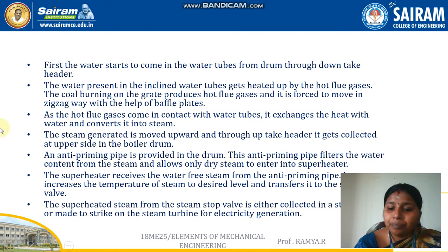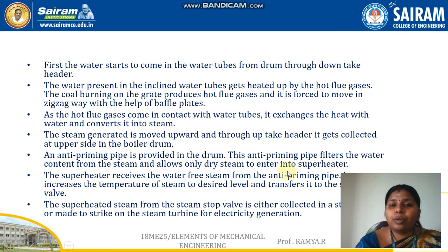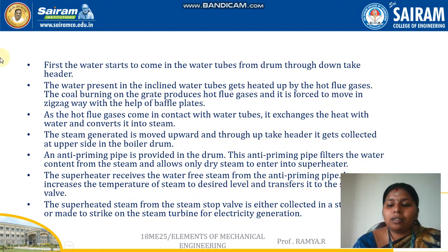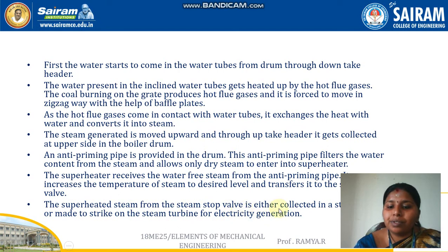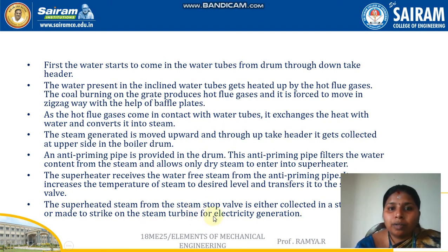The steam generated moves upward through the uptake header and is collected at the upper side of the boiler drum. An anti-priming pipe in the drum filters out water content and allows only dry steam to enter the superheater. The superheater increases the steam temperature to the desired level and transfers it to the steam stop valve. The superheated steam is then either collected in a steam drum or sent directly to a steam turbine for electricity generation.